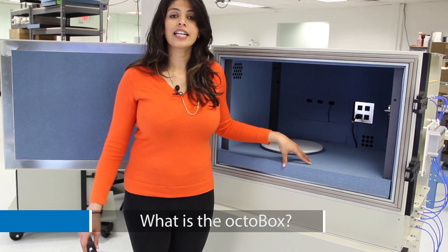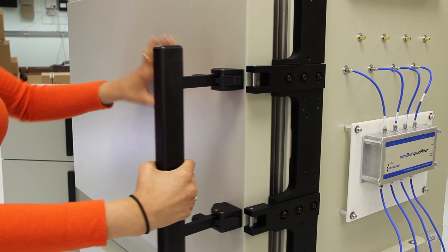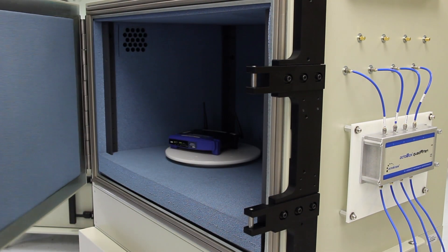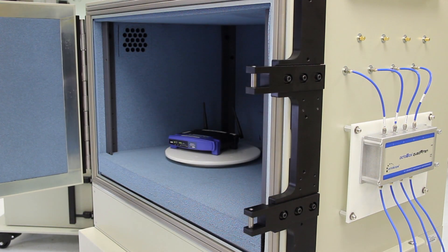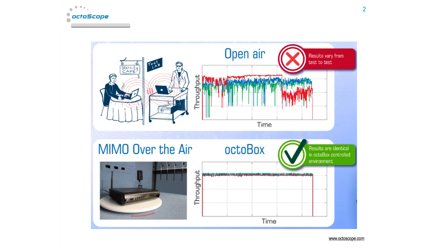The octoBox is a small stackable anechoic chamber used for testing wireless devices and systems. It isolates the device under test from external interferences and creates a stable environment to achieve repeatable throughput measurements.